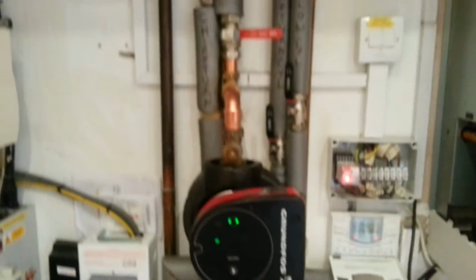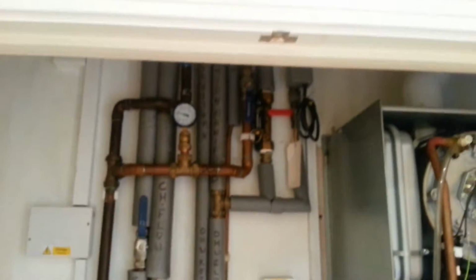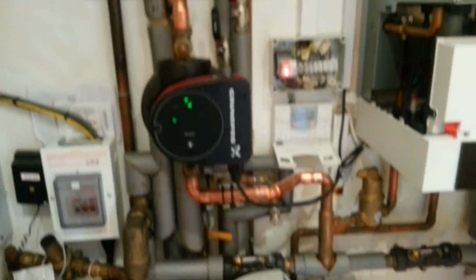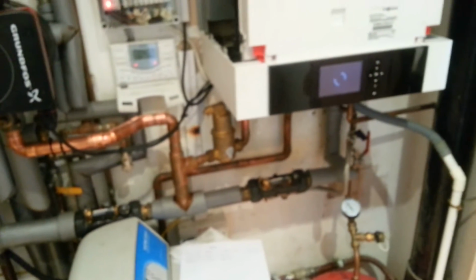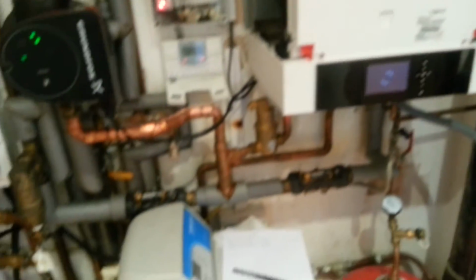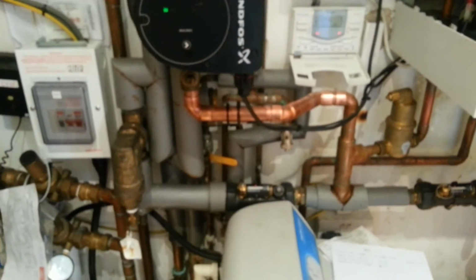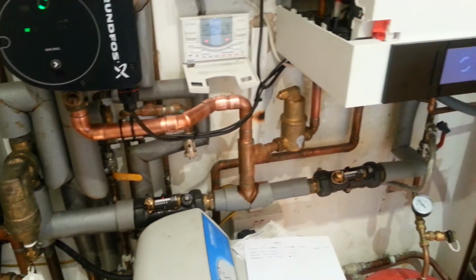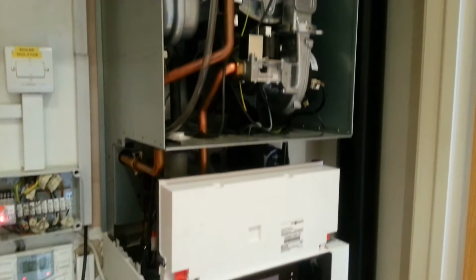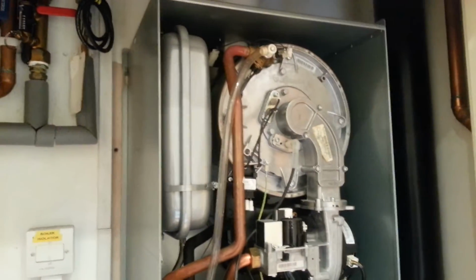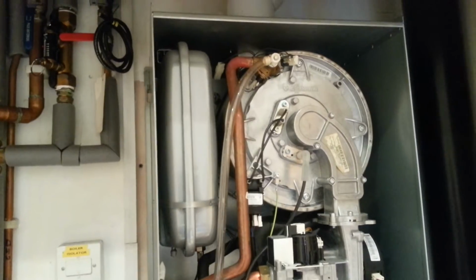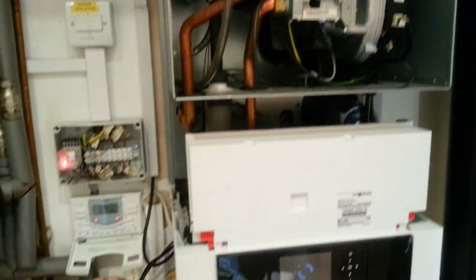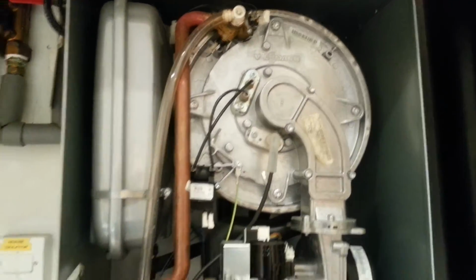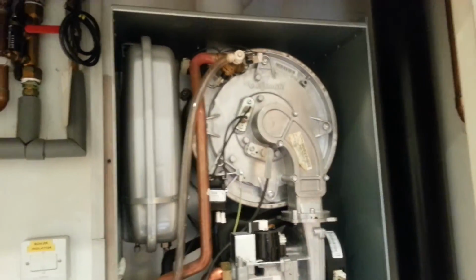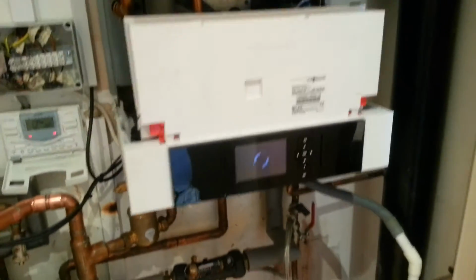So yeah, as you can see, pipework everywhere. This was an aluminium heat exchanger boiler here before. Lasted about 3 years before the heat exchanger disintegrated, as the pH level in the system wasn't suitable for aluminium, and basically caused the collapse of the boiler, as it does in many aluminium heat exchanger boilers. Done quite a few of these, lots of Kestons, quite a few Worcesters, but the new boiler, Viessmann 200 stainless steel heat exchanger, no problems with that. That'll see my customer out, I'm sure.